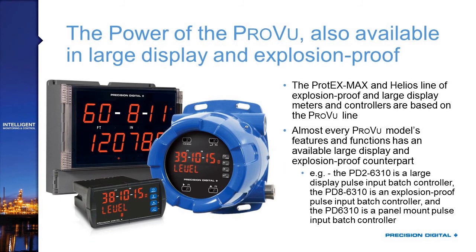Not only is the ProVu available in the Protex Max variety, but we also have a ProVu-based device in our new Helios product — a large display field-mount device with a 1.8-inch display for each line. Like the Protex Max, it's available in all the ProVu varieties, including feet-and-inches, process indicator, and rate totalizer. It can have all the same outputs: 4-20mA output, up to four relays, and 24-volt supplies, plus all the new features we're about to discuss.